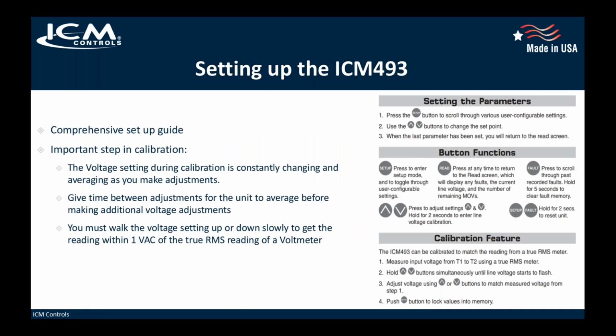Now, how do you do that on the 493? Well, I've given you a blurb here. We can look at this later. But basically, there's a process through the front panel to adjust the voltage read by the ICM 493 to the true RMS reading. When it's doing this calibration, it's not just a quick press of a button and it goes right to it. It's constantly averaging the voltage, so it's a dynamically changing average. So you've got to let it settle out between settings.